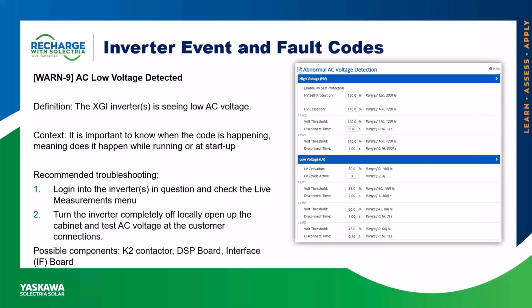If you are seeing values on the measurements menu, similar to Warn 2, along with the recovery settings, you can also look at the abnormal AC voltage detection parameters found under the inverter functions and AC voltage and frequency trip settings, which is the screenshot you see on this slide. This is important to view, especially if this code is occurring during the day as opposed to at startup. If the AC voltages are dropping below the programmed threshold, then Warn 9 will record under the inverter's event and fault log.